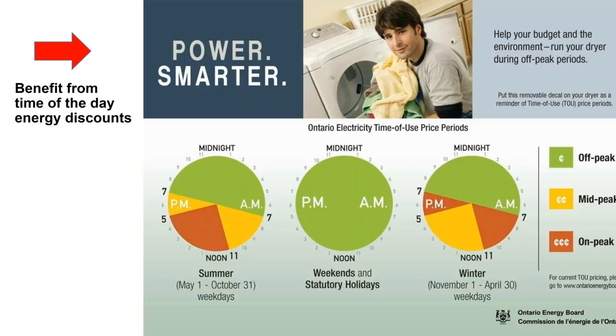An obvious direct benefit from this cycle is that certain utility companies employ time-of-day electrical use pricing. Coincidentally, typical unoccupied hours are correlated to off-peak hours, so when you pre-cool and pre-heat the space you're taking advantage of lower rates. Using the building as a battery makes it highly practical and allows supercharging the structure at night highly efficiently — whether in a purely mechanical mode, or where the ventilation fan can pick up a lot of free cooling. Not only is it an efficient way of doing things, but it really improves interior air quality considerably.